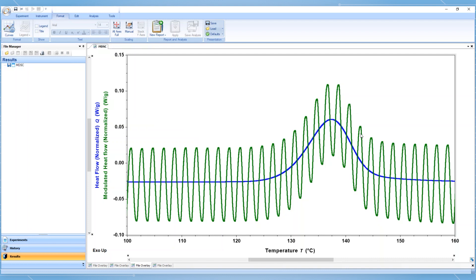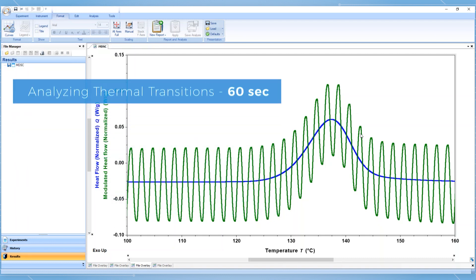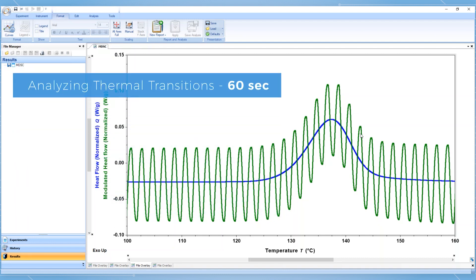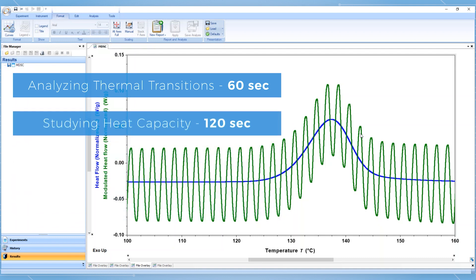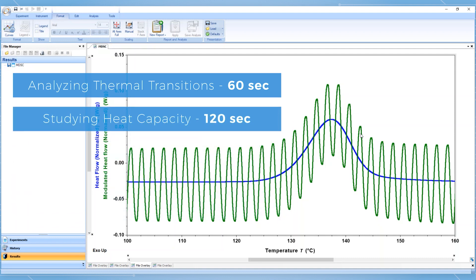In general, TA Instruments recommends that when analyzing thermal transitions with MDSC, a period of 60 seconds be used. When performing heat capacity measurements, we recommend a period of 120 seconds.